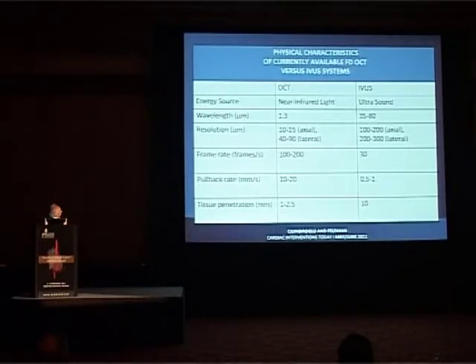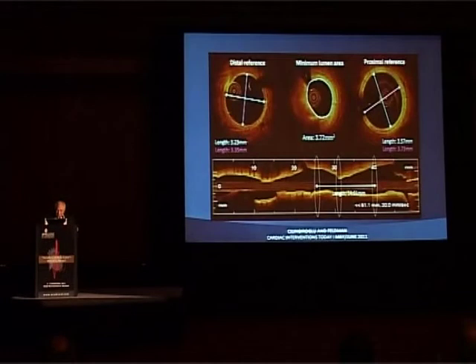Because of this difference in resolution between these two systems, optical coherence tomography is good for the very near field, whereas IVUS is used for the far field, giving much more thickness of vessel penetration. So tissue penetration is much greater for IVUS, but if you want to see the luminal surface, OCT is a much better technology.